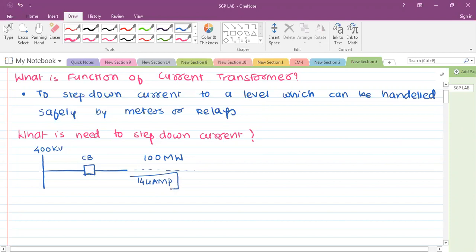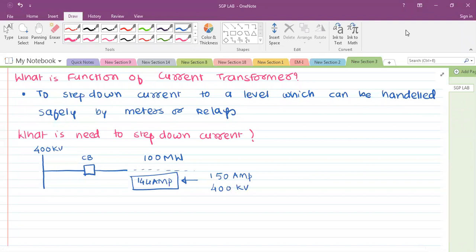Now, is it feasible to design a meter which can be directly connected to the line and which can measure 144 ampere? The meter rating must be 150 ampere, considering this is the rated current, and its voltage rating must be 400 kV. Is it feasible to design this, considering the cost, the size, everything? No. And that is why meters and relays are not directly connected to the lines.